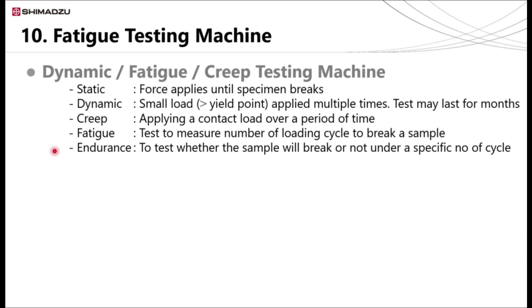When selecting a fatigue or a dynamic testing machine, unlike the static test systems, there are many parameters which have to be carefully selected. Type of the test, high cycle or low cycle, loading mode, compression mode, tensile mode, bending mode, waveform, sine, triangular, and the kind of test piece, flat, round, maximum force or maximum displacement, speed and frequency, amplitude, test control, force control, strain gauge control or displacement control, etc. We have a ready-made sheet available which helps you in selecting a fatigue testing machine which suits your requirement. You can contact us for these sheets and we are happy to send the PDF copy.